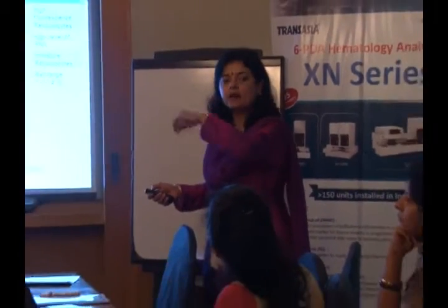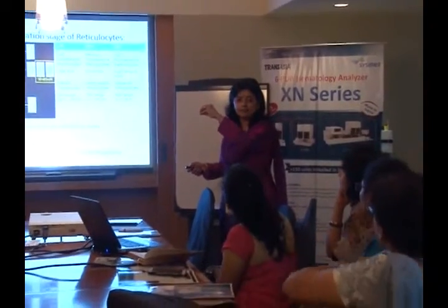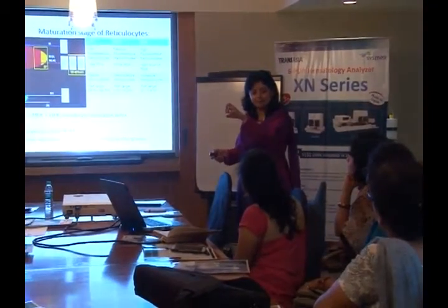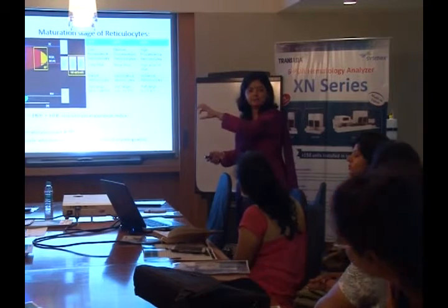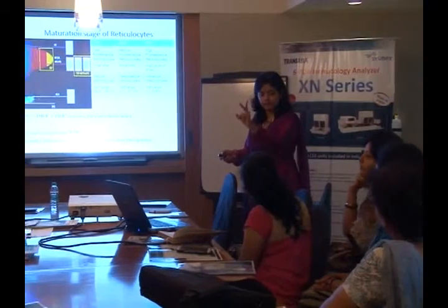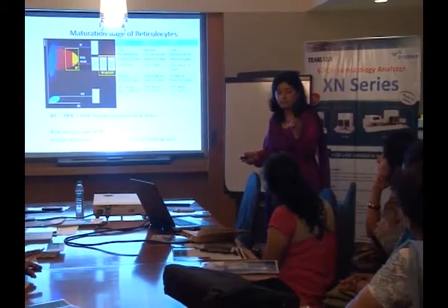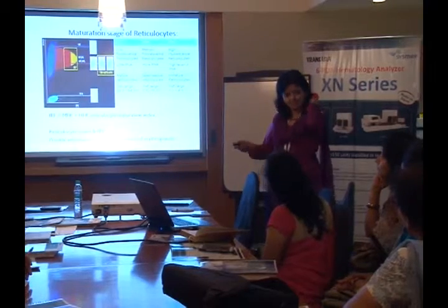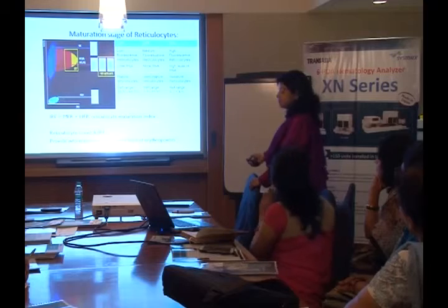What is the relationship of platelet? There is some similarity. In the same channel they are getting counted by the same RNA dye. I will come to that. So immature platelets have RNA in them. So the same stain is taking the platelets also. So the same reticulocyte channel, we are using it for reticulocyte count and the platelet optical. Because the other platelet count that you are getting normally is the impedance. This is optical count. So it is cross verification of platelets.